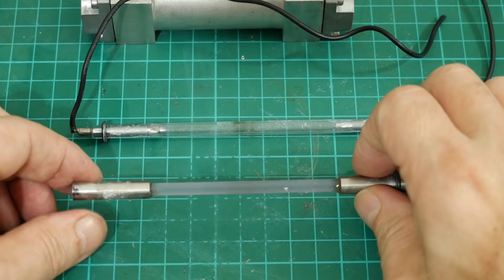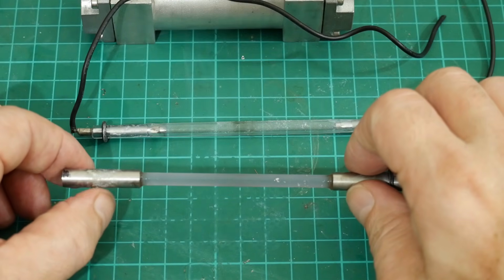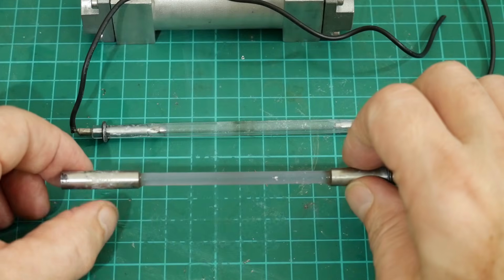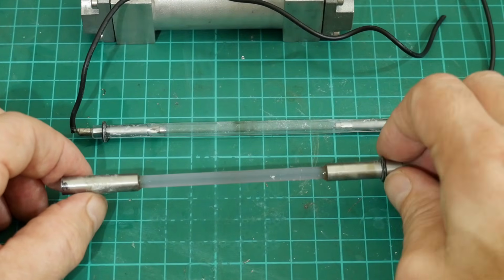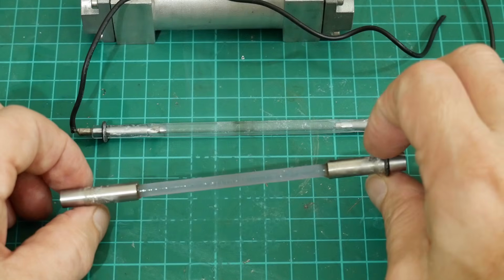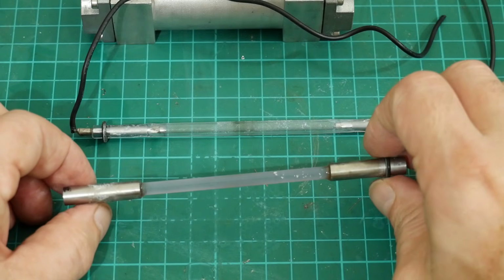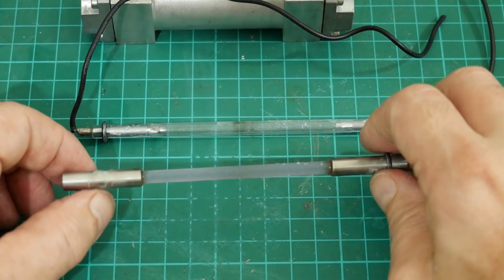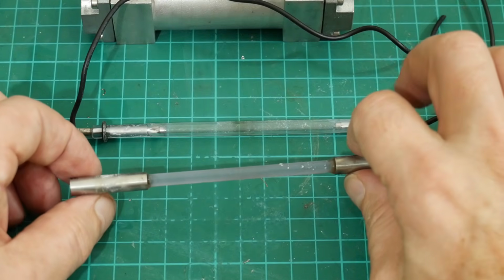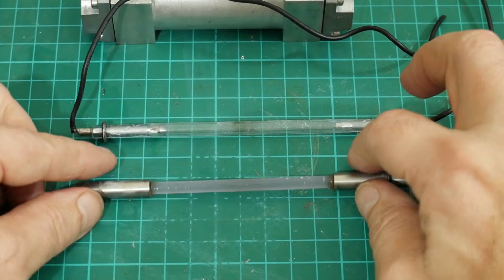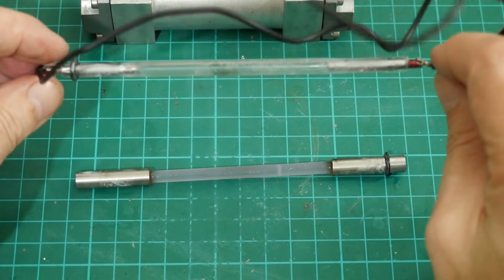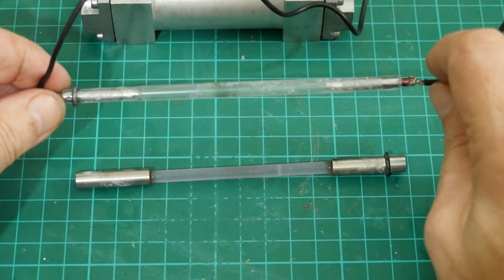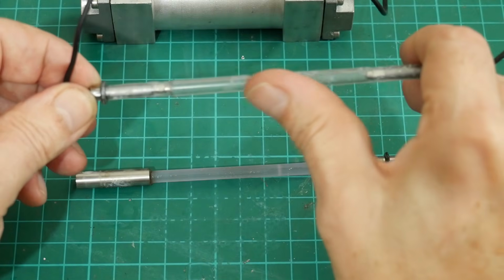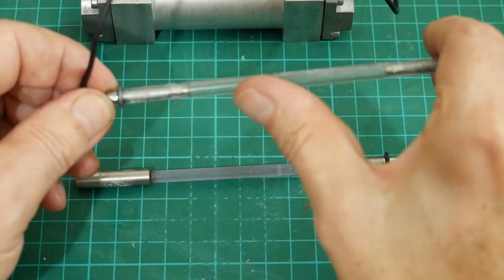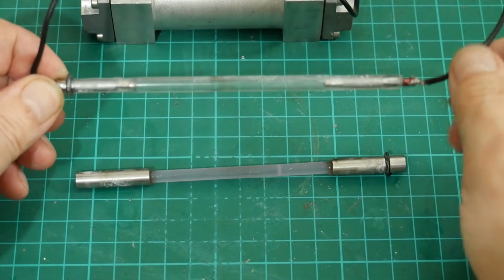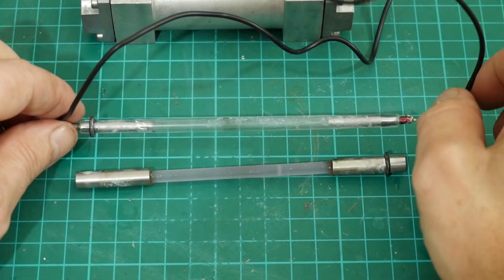We can see some corrosion on the rod holders at the end here, some kind of deposit, probably calcium or something. This has evidently been run with tap water. These things should always be run with deionized water because otherwise the aluminium corrodes and all sorts of nasty stuff happens. But the rod is unbroken and it looks relatively clean. Very nice. The flash lamp as well, there looks to be some discoloration on there, but it actually looks like it's probably in serviceable condition. Again, there's a buildup of some kind of gunk or film on the surface of the lamp, and I'll clean this off with some isopropyl alcohol before reassembly.